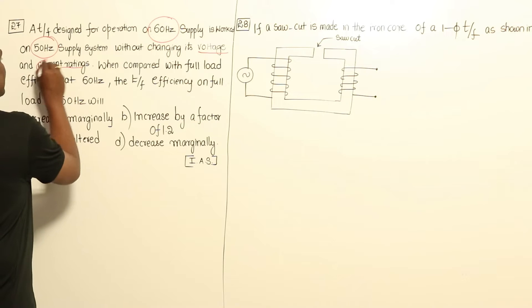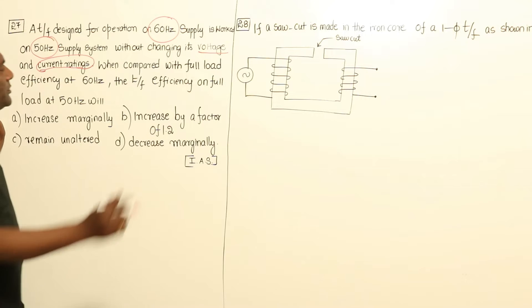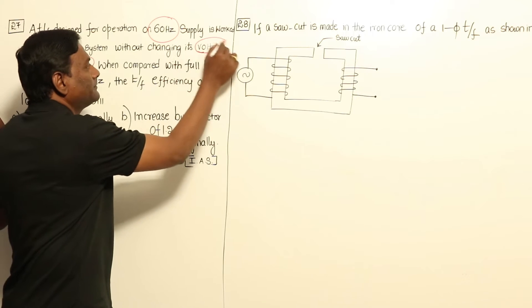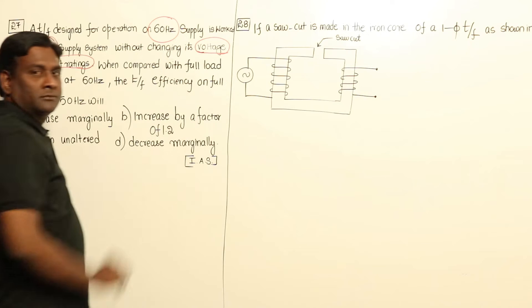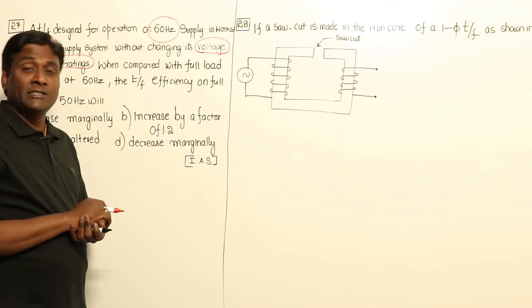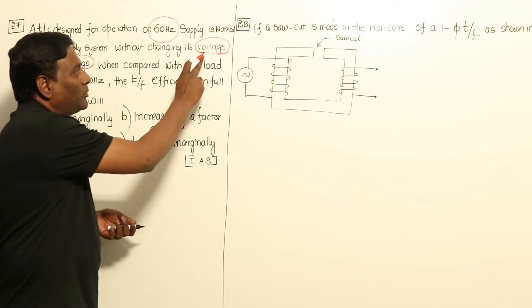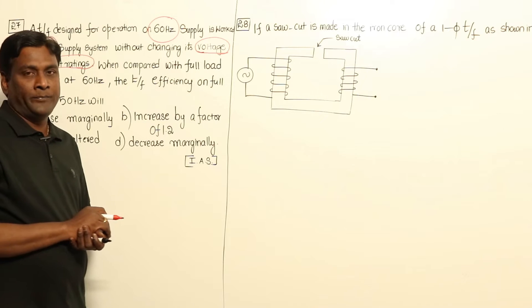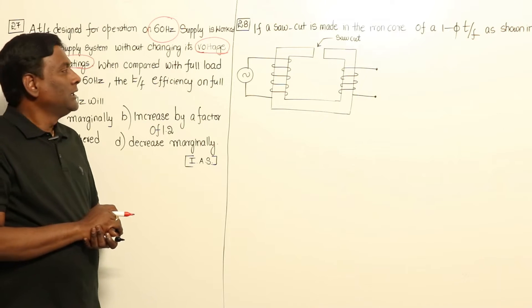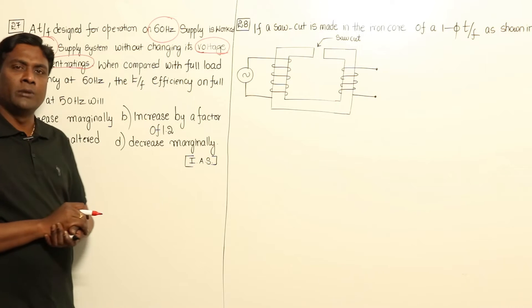Since the current ratings are the same, copper losses will be the same because current is same. And now, if you see voltage ratings are the same, it means eddy current losses are independent of frequency and will be decided by voltage only. So the moment voltage ratings are same, eddy current losses also will be same.